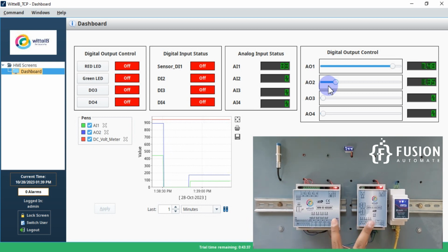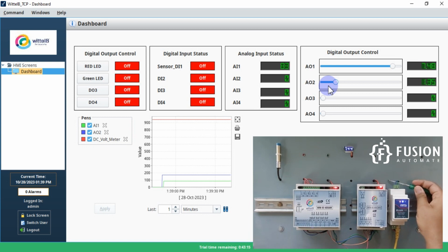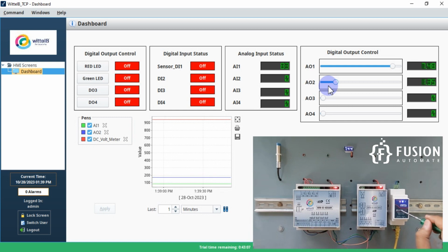This card also comes in the form of a Modbus TCP card. This is the Modbus serial communication card. You can see this green and blue cable here. This green and blue cable is for Modbus serial communication. I have looped this cable from here to here and then from here to here, as you can see. Green and blue cable. This ZLAN5143D gateway will convert Modbus serial data into Modbus TCP data, and from this yellow LAN cable we are going to communicate with our Ignition SCADA software.